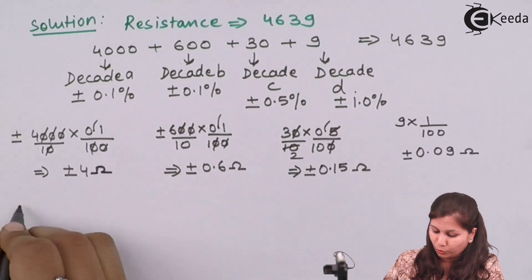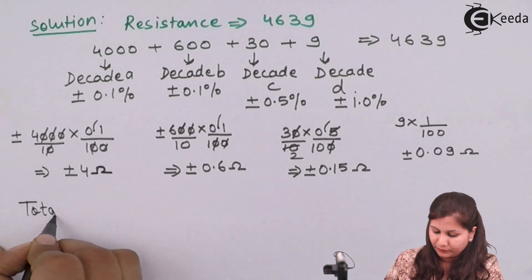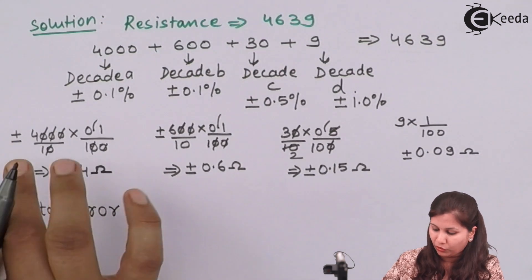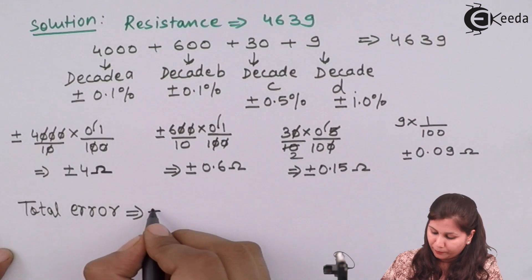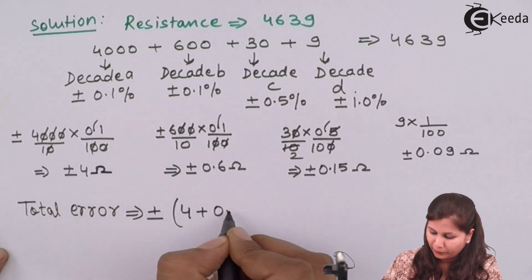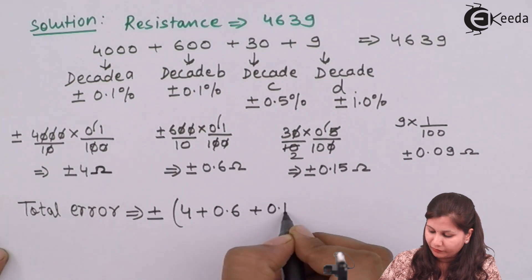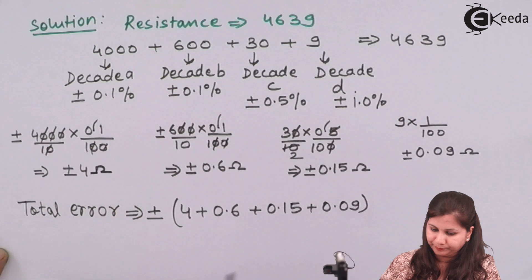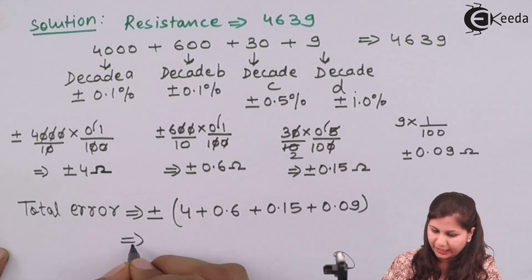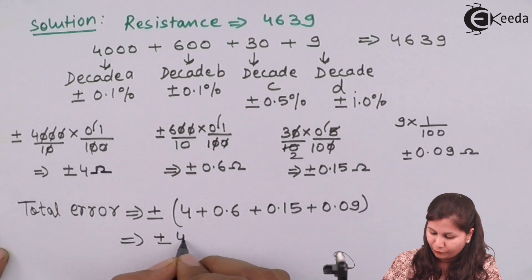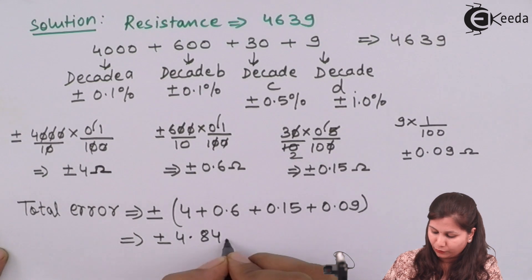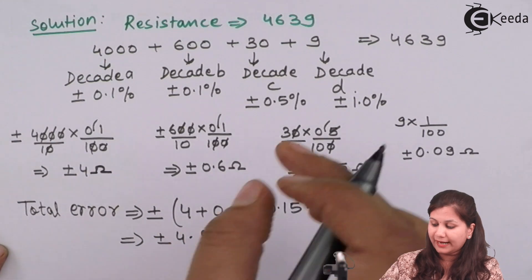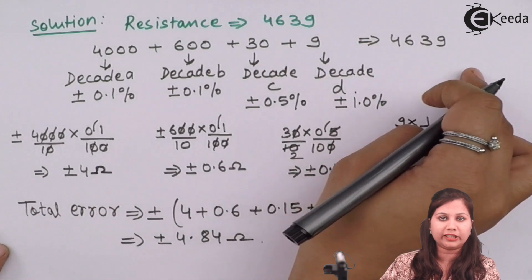The total error is the sum of all individual errors: ±(4 + 0.6 + 0.15 + 0.09) = ±4.84 ohms. This is the total error occurring at the reading of 4639 ohms.